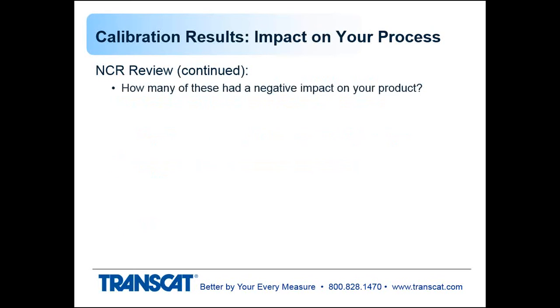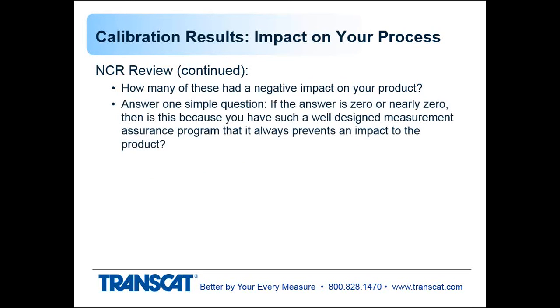So of the out-of-tolerance NCRs, how many of those had a negative impact on the product? And if the answer is 0 or very near 0, then it could be for one of 2 reasons. You either have a very robust quality program that makes sure there's enough buffer between the instrument tolerances for calibration and the product acceptance tolerances. And I've seen that in many cases. But if it's near 0 for another reason, it could be because you're not having good, thorough NCR out-of-tolerance impact reviews.